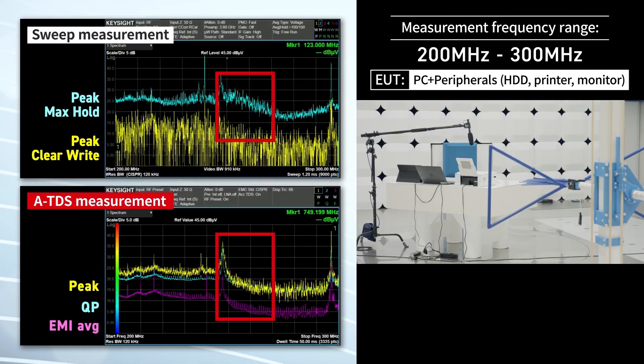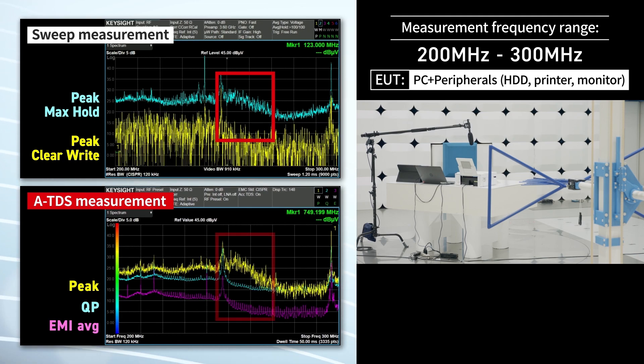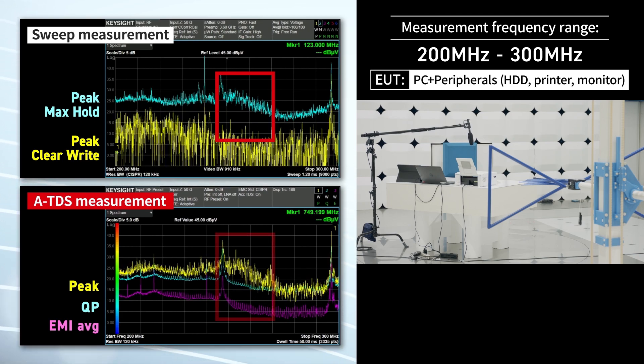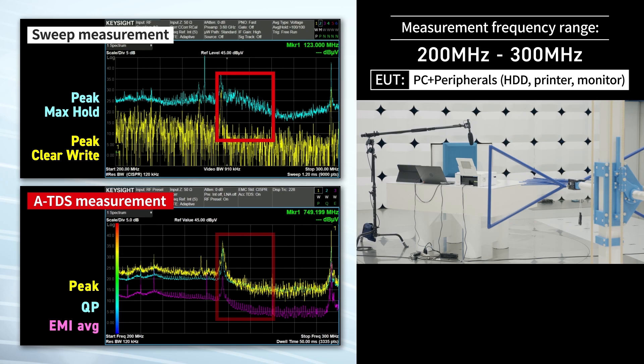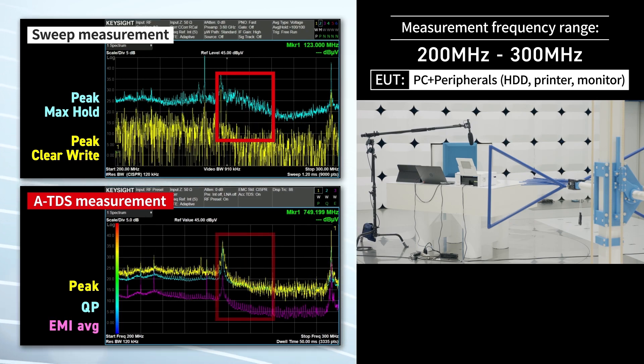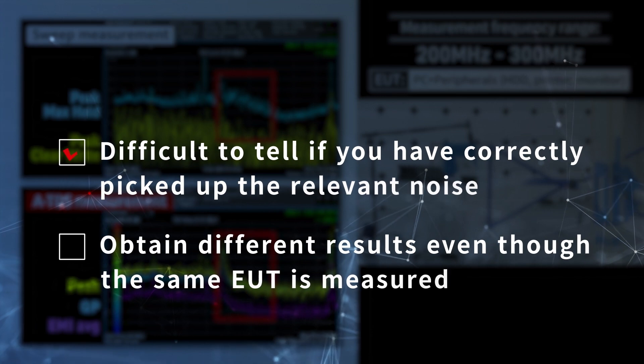We looked closely at the place where we had seen a high noise level during the sweep measurement using the peak detector and max hold. Using the ATDS feature with the QP detector turned on, we can easily tell the level was not as severe as we originally thought. Like this, we can select the right noise.